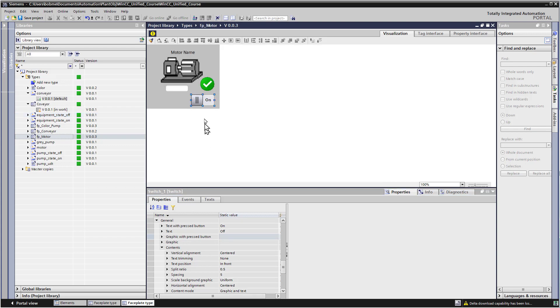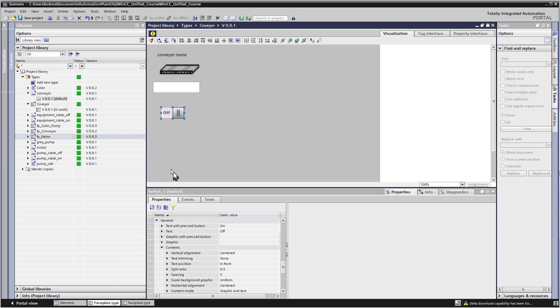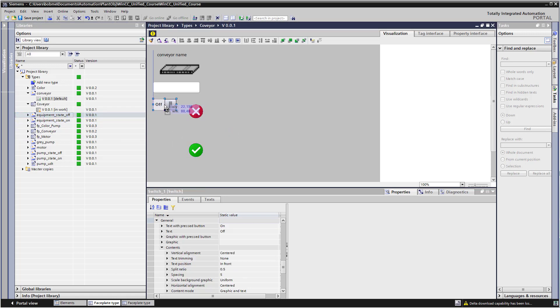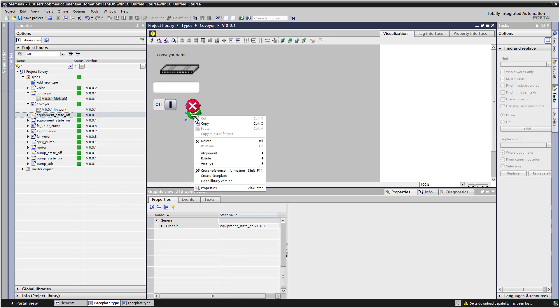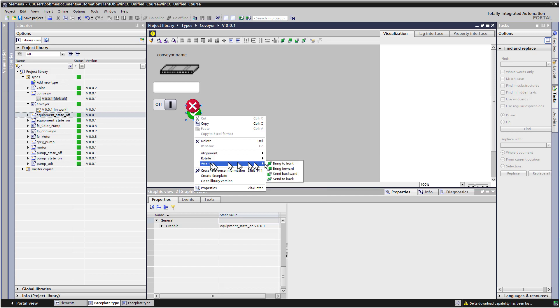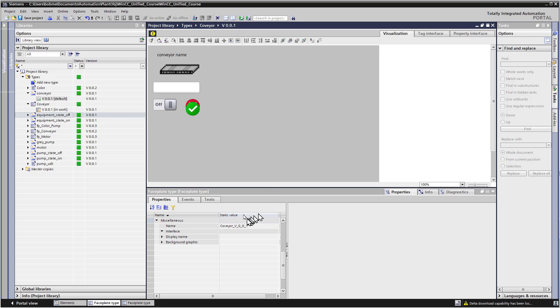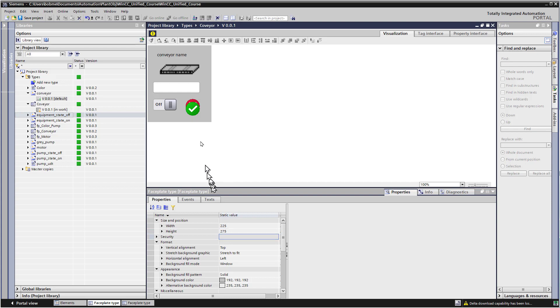And then if you remember from our earlier lesson where we had our color pump, which looks like this, we had these two graphic images. And we just had a Boolean that would either hide or show the green checkbox, and there's a red X under that. So we're going to do the same thing back on our faceplate. So we've got equipment state on and equipment state off graphics. And so what I'll do is just kind of put these guys right here. And I'm going to right click and do arrange, bring to front on this guy. And I'm just going to leave it a little offset so you can see it behind. But let's get our size right on our faceplate. So let's say our width is about 225. And then our height, let's say about 275. That looks about right.